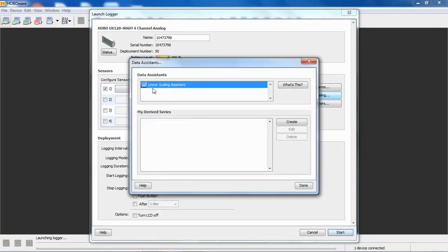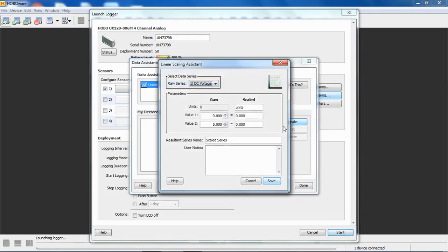So we click on that, and this is where we get to the linear scaling assistant. And again, we're doing this as we're setting up the device. So we're going to click on Create, and this is where we can set our relationship. Our raw signal is in voltage or current or whatever the output of that sensor is. The scaled is our engineering units, or how we want the data to be represented in the data file.